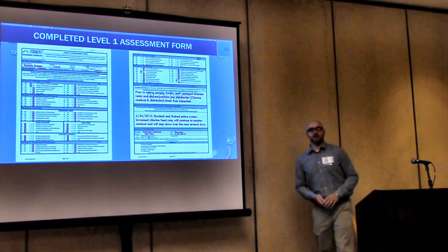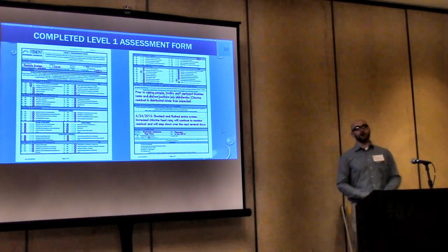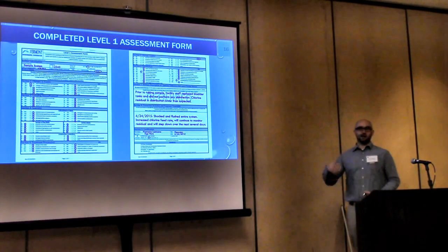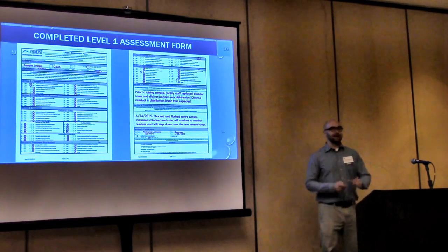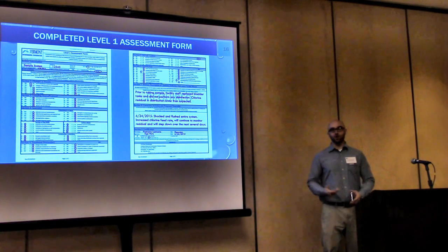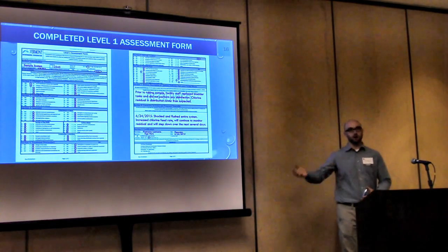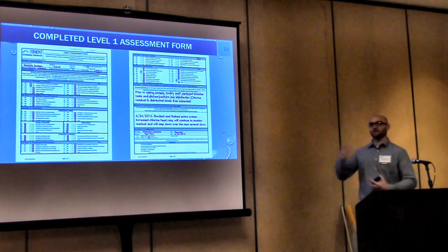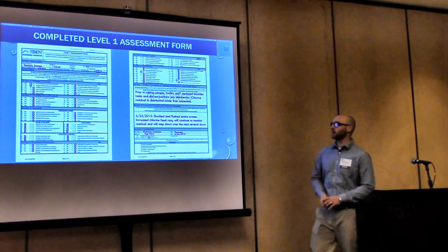So you sample the south side of town, you've always sampled the south side of town. And then all of a sudden, the dairy that's on the south side of town closes up, you've got a 10-inch main going to nowhere. Probably not the best place to take a sample because you know you're not going to have the water use out there and the water age and all that sort of stuff. So that sort of stuff can change in the system as things go on.